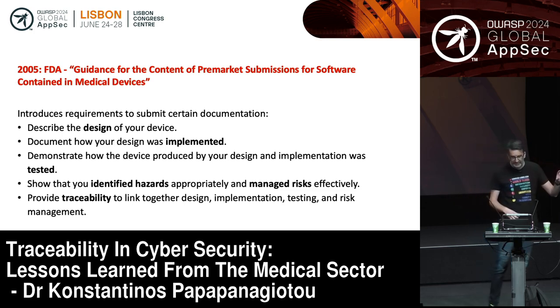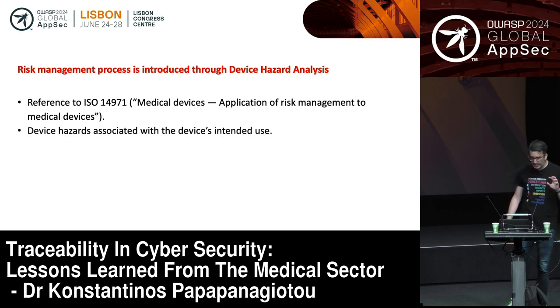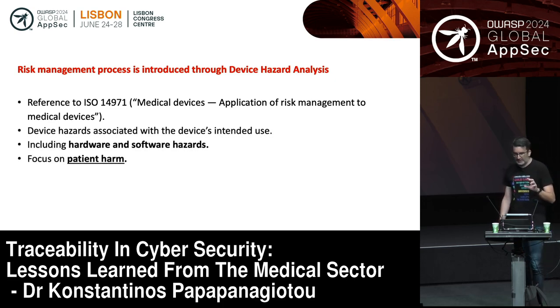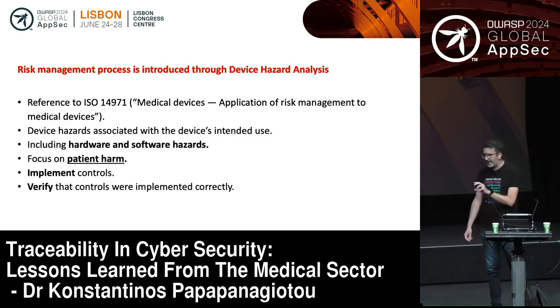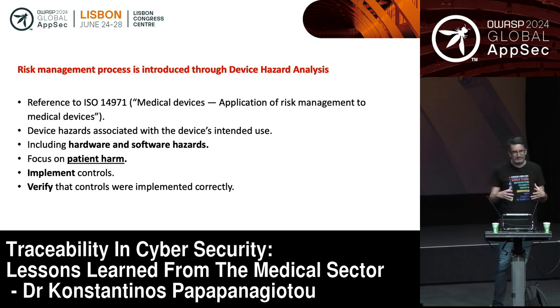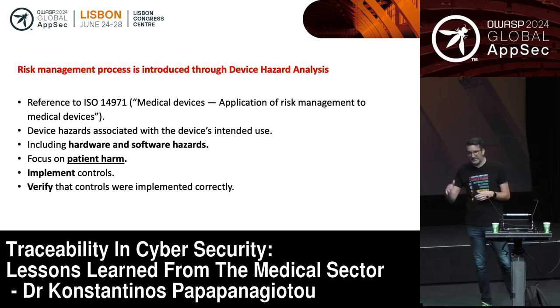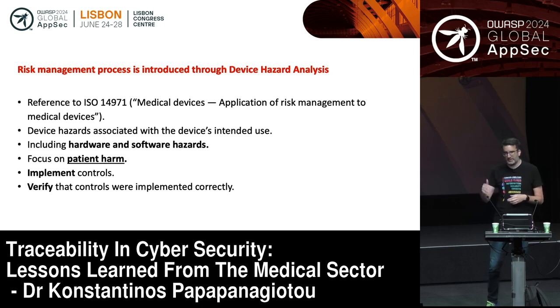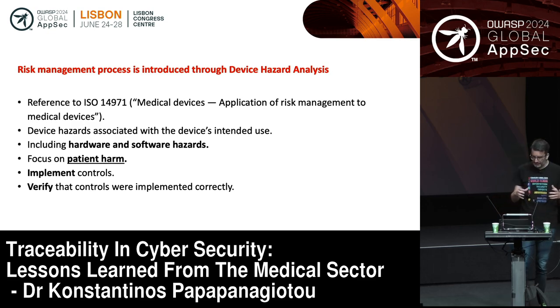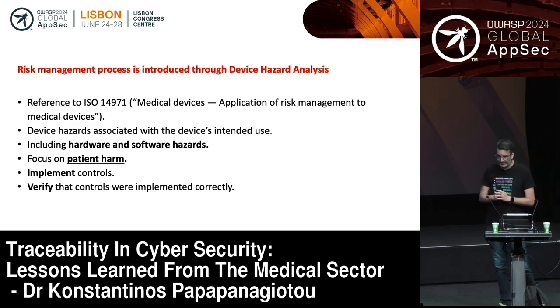So this was back in 2005. I think one of the most important concepts here has to do with risk management. In 2005, FDA says that if you are going to develop a medical device, you need to manage your risks. Managing risks means device hazard analysis—that's what FDA calls risk management. It makes a reference to ISO 14971, which is very popular in the medical sector, in the healthcare sector.